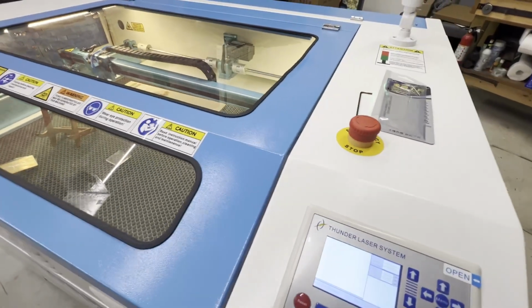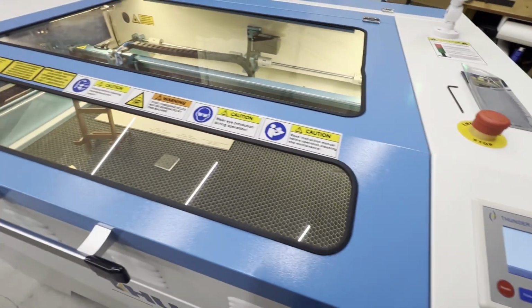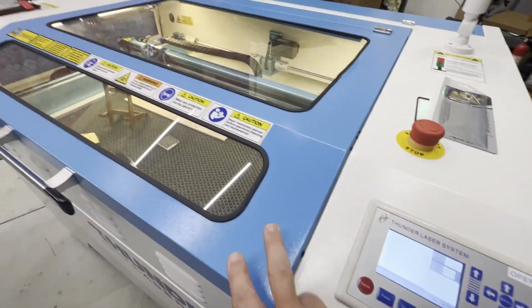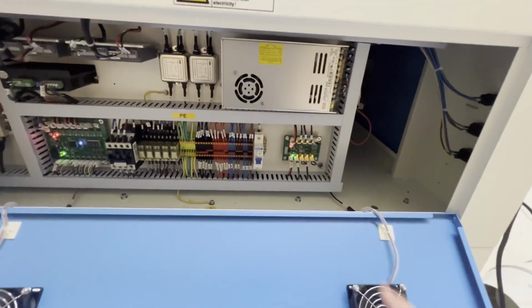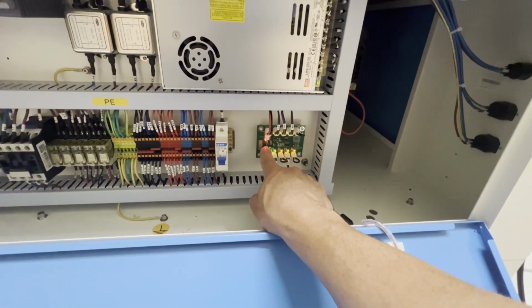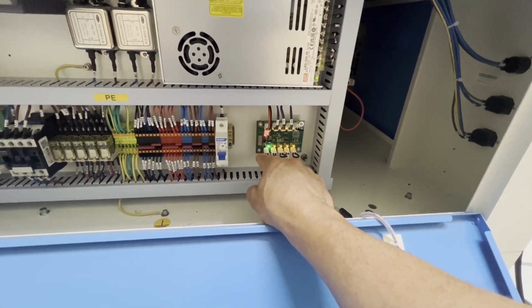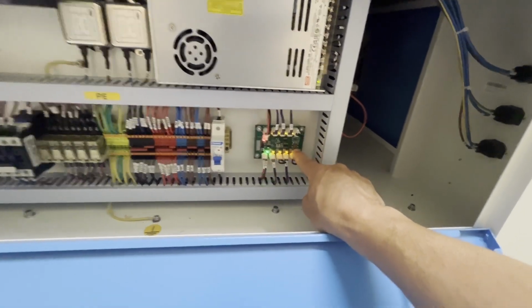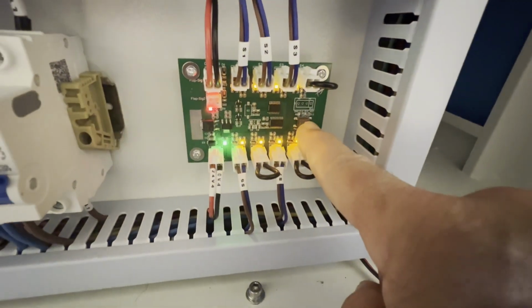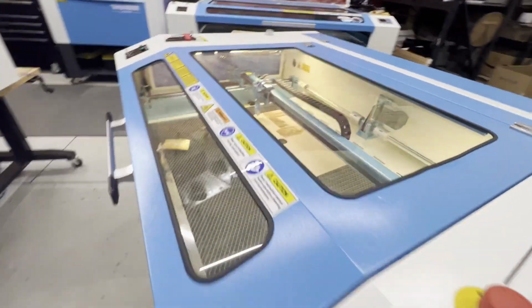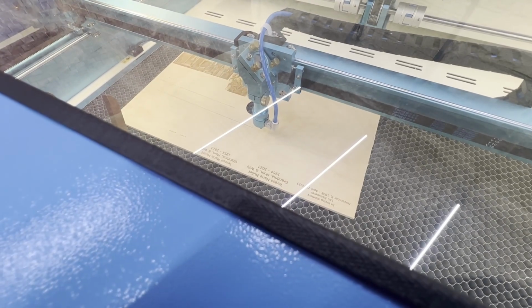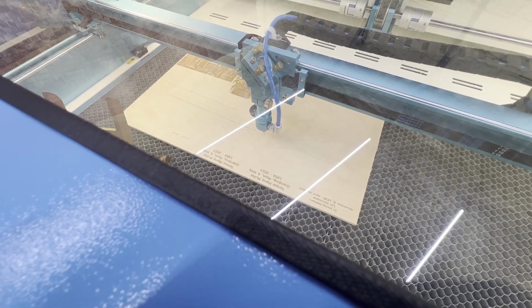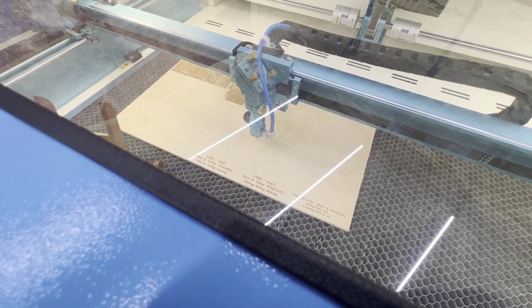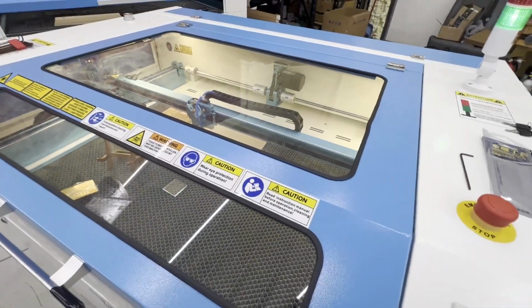One thing I like to do before I even get started connecting to the computer is test my laser pulse. To do that, we need to have the door closed, or we can go down to the door board and basically deactivate it, and it'll stay deactivated until we restart the machine. So I can hit the button here, and that will turn the door board off, basically bypassing our sensors so that we can test. And I will hit the pulse button and make sure that I am getting some type of pulse from the laser, just to double check and make sure everything is up and running and functional.